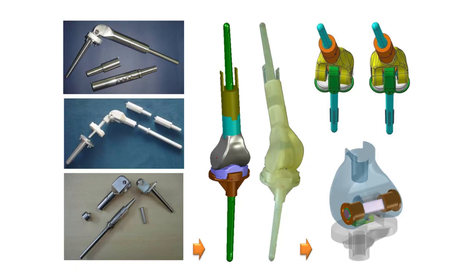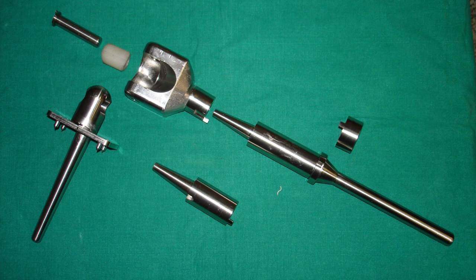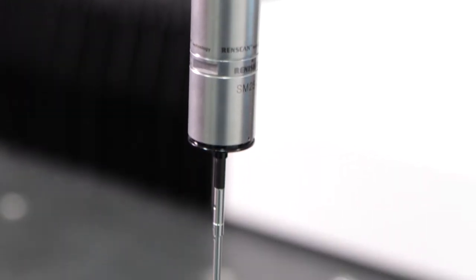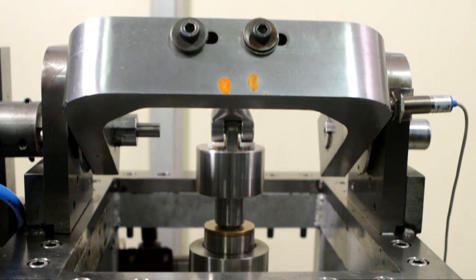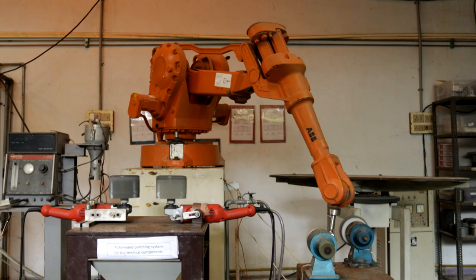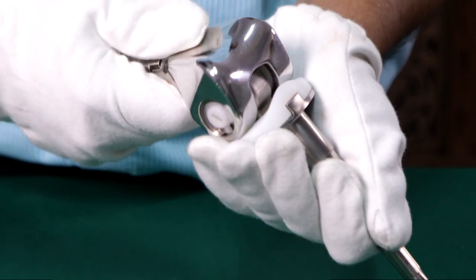TKP is not just one product — it is actually a system of products. We have the main device in multiple components, then we have surgical instruments, quite a number of them. We also later built a walking machine to test the joint for millions of cycles to make sure it is safe before human trials. The first versions were developed in OrthoCAD lab at IIT Bombay and later taken over by NFTDC Hyderabad. We are making it by state-of-the-art computer-controlled processes using very high-quality materials and elaborate testing mechanisms for both input materials and the final product — tested in a knee simulator for over 10 million cycles. We are confident it would be a superior product that restores much of the natural functions of the knee joint.